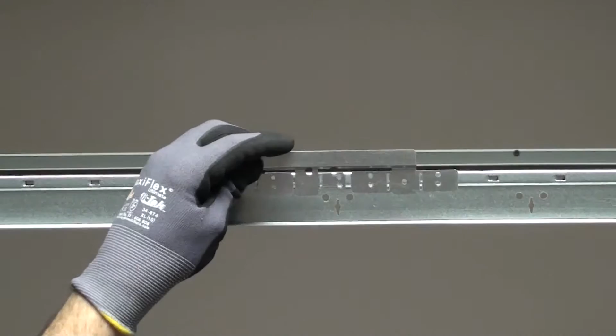Begin the installation by folding out the center indexing tab on the first UMB 90 degrees and insert it through the cross tee hole of the main tee. Then bend it back 90 degrees. For a continuous condition, 2 utility module brackets will be required. Repeat the previous steps on the opposing side.